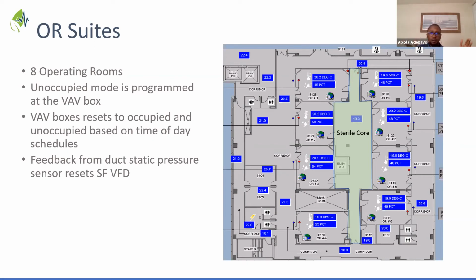We know the occupancy hours, so there was no need to program it based on an occupancy sensor sensing occupancy in the operating room. We also created a switch that could turn it to occupied mode instantaneously. That's for emergency situations, which we don't emphasize, but it's there to be used. If there's something else, all they need to do is reach out to the operations team on site and flip the switch straight up.